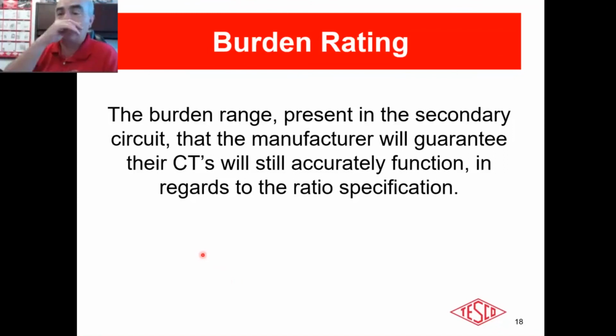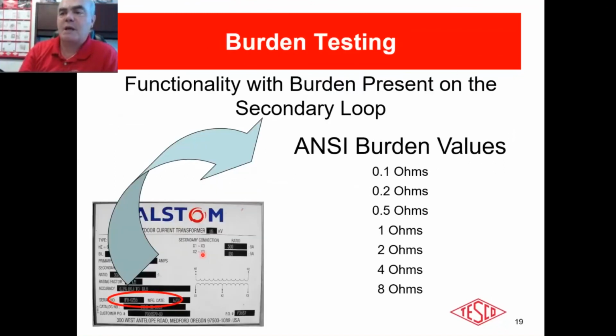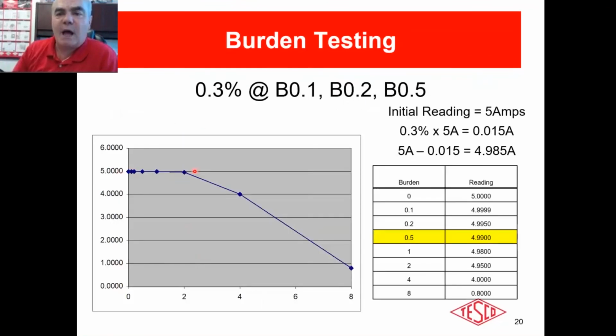All right, so this burden test is important because what we want to understand is that, okay, I can take some burden here. I can take some burden and really not see any significant loss of accuracy. Okay, you can see, between 0 and 0.5, I really didn't see a very significant loss at all. I'm well within my specs. So we're doing okay here. That's why we're checking to burden. So doing a burden test is important to make sure that the transformer can handle a certain amount of burden. Now, this transformer, as good as it is, as perfect as it is, if I put too long a run of wire, I allow too much corrosion, I have some loose connections in there.